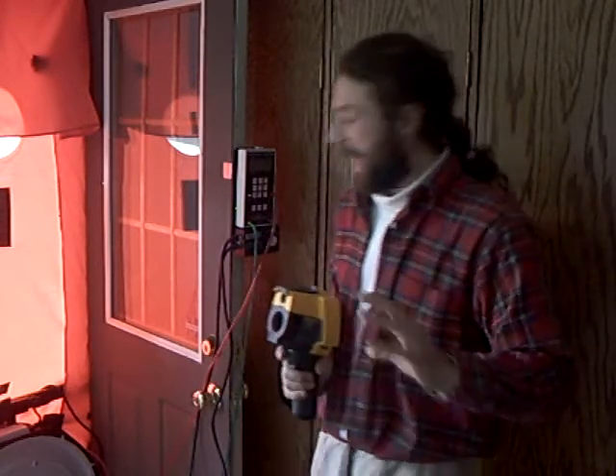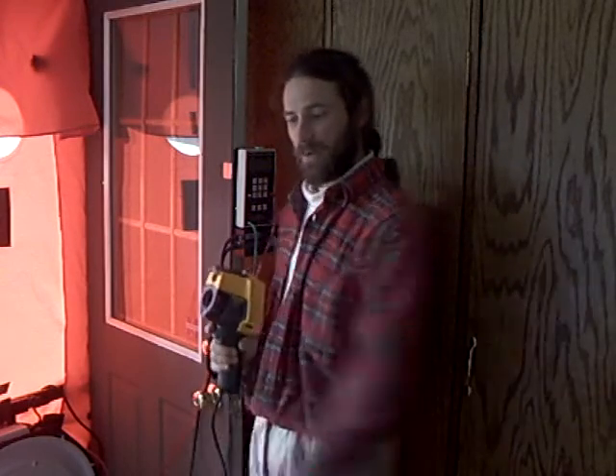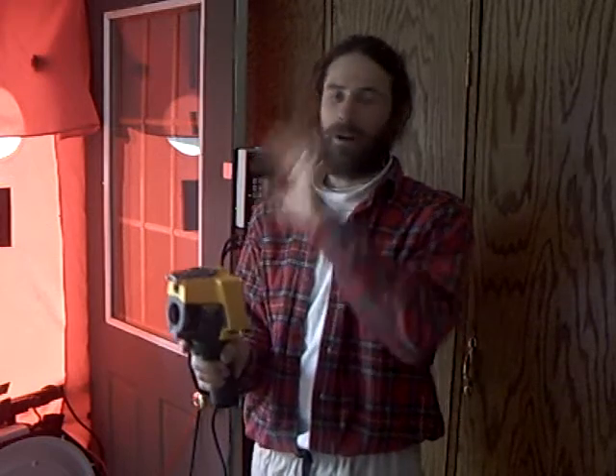I have a thermal imaging scanner that detects surface temperatures only. It's not like an x-ray. I can't see through a wall, but I can see the temperature of an exterior surface. So as this blower door is depressurizing the house, blowing air out, air is being replaced through all of the cracks or breaches in your air barrier. That shows up in a color rendered picture of hot and cold, basically. So we get to see on this cold day, cold air being pulled in and striking those exterior surfaces immediately changes temperature. The infrared camera shows that very accurately.